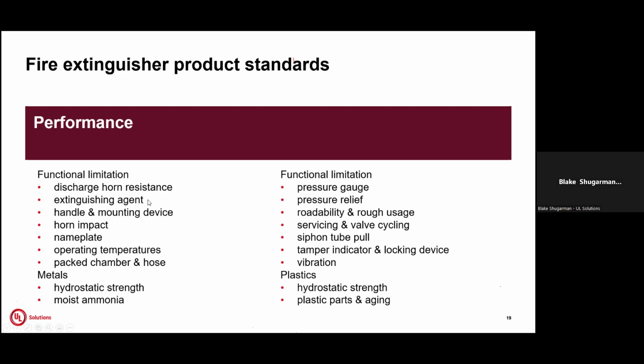We have extinguishing agent tests, handle and mounting device tests to make sure that when it is stored, it will maintain its integrity in storage and not sustain any breakage due to external loads being applied. We have a horn impact test, nameplate tests for adhesion, abrasion, and exposures to different types of environments. We have operating temperature tests, and for dry chemical, we have packed chamber and packed hose tests.